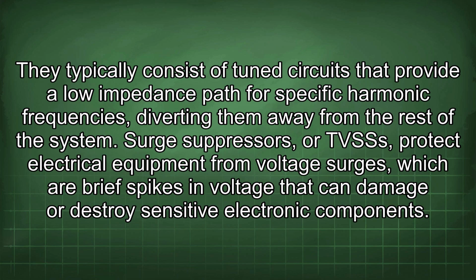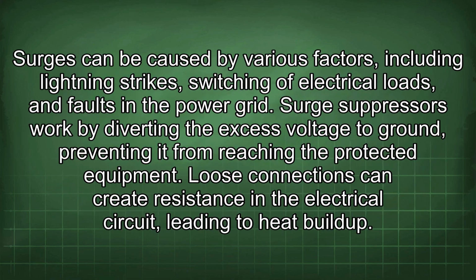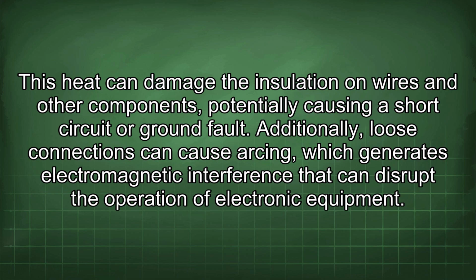Surge suppressors, or TVSSs, protect electrical equipment from voltage surges, which are brief spikes in voltage that can damage or destroy sensitive electronic components. Surges can be caused by various factors, including lightning strikes, switching of electrical loads, and faults in the power grid. Surge suppressors work by diverting the excess voltage to ground, preventing it from reaching the protected equipment. Loose connections can create resistance in the electrical circuit, leading to heat buildup. This heat can damage the insulation on wires and other components, potentially causing a short circuit or ground fault. Additionally, loose connections can cause arcing, which generates electromagnetic interference that can disrupt the operation of electronic equipment.